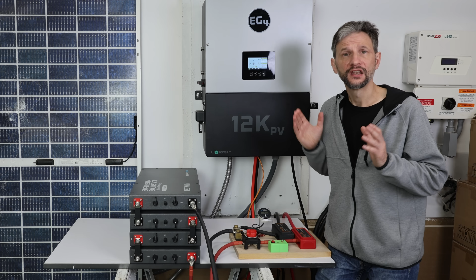Now with the 12 volt setup, we were pulling over 200 amps from the battery to support only a 2500 watt load. Now, when I put these in series, I still only have 200 amps available, but at 51 volts, that can put out a continuous 10,200 watts. At 12 volts, we were overloading the BMS at only 2500 watts. The inverter can easily export 8 kilowatts, and that's sufficient for my standard level 2 EV charger.